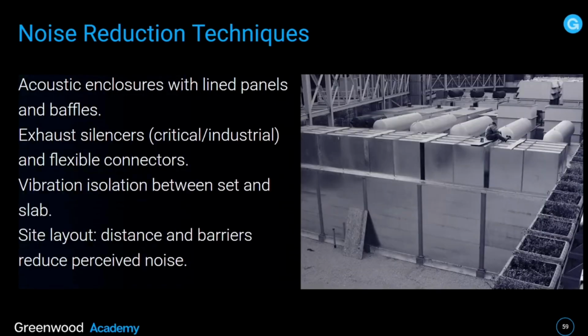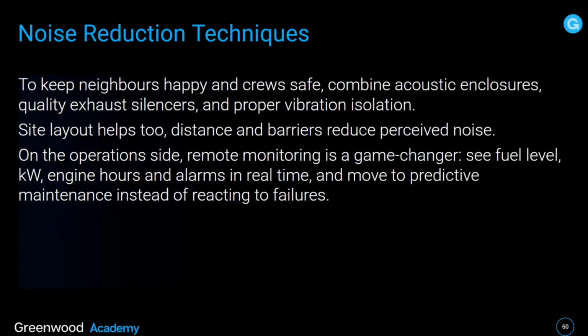Now, acoustic enclosures with lined panels and baffles is an option. Exhaust silencers, critical, industrial, and flexible connectors, vibration isolation between set and slab, site layout, distance and barriers, and reduced perceived noise. Remember, noise has a logarithmic component, and as I mentioned before, the difference between 55 decibels and 65 decibels is considerable. Noise reduction techniques.